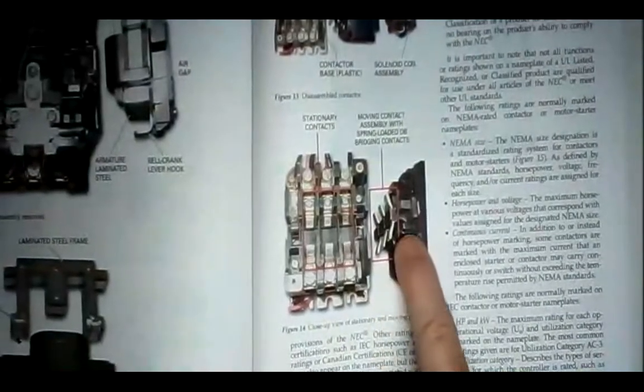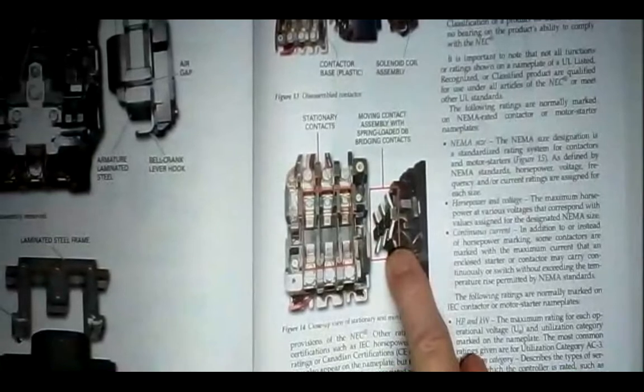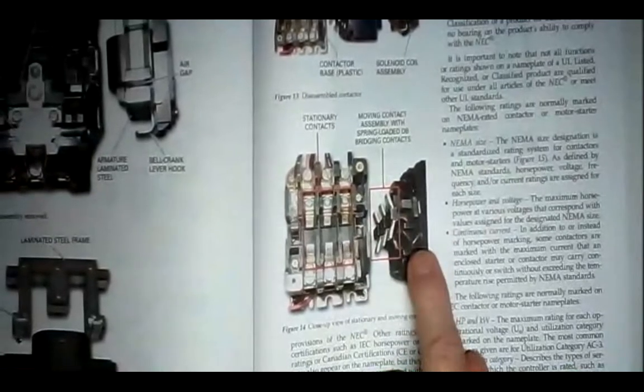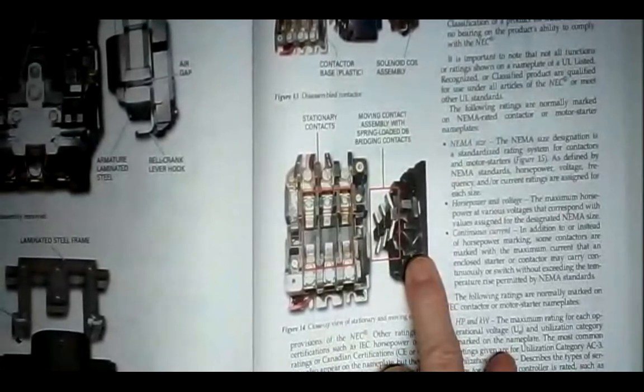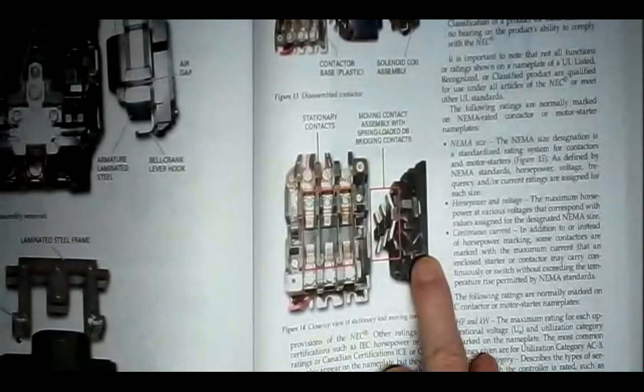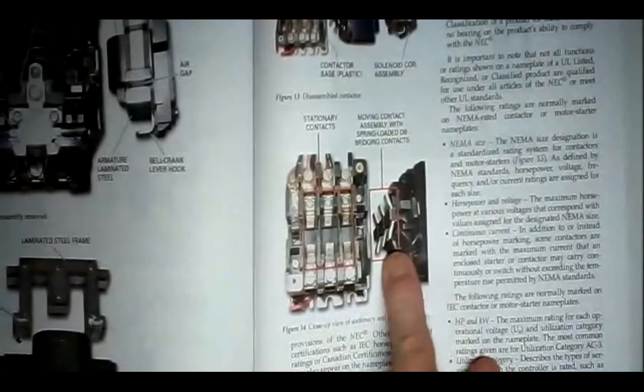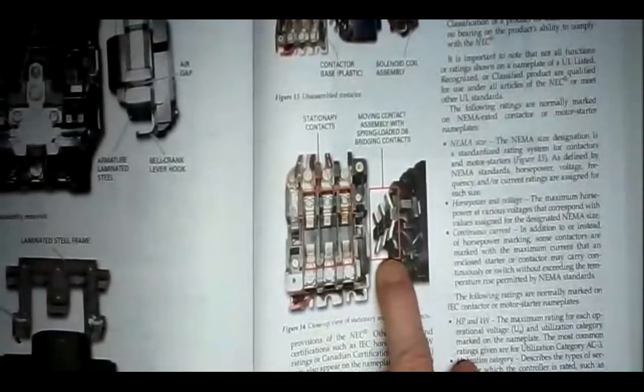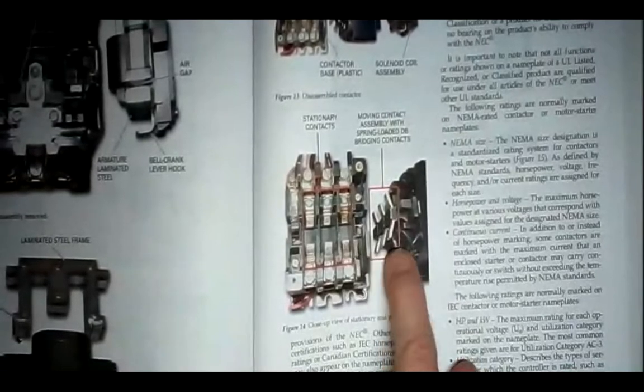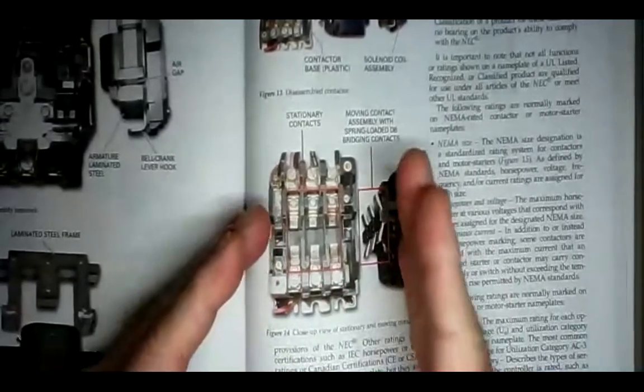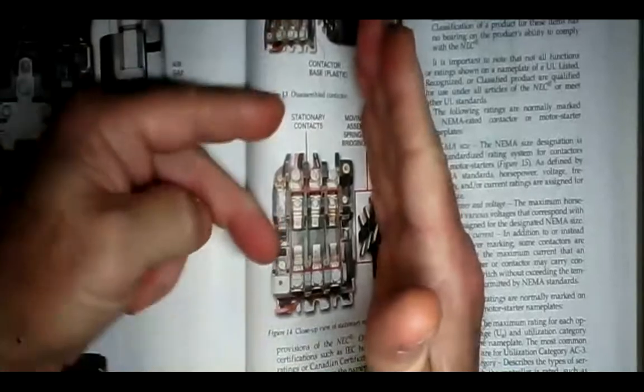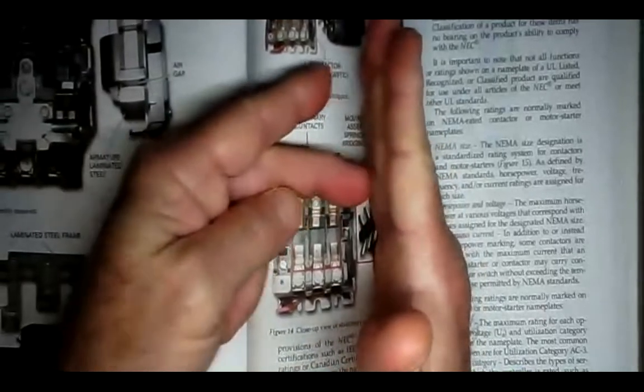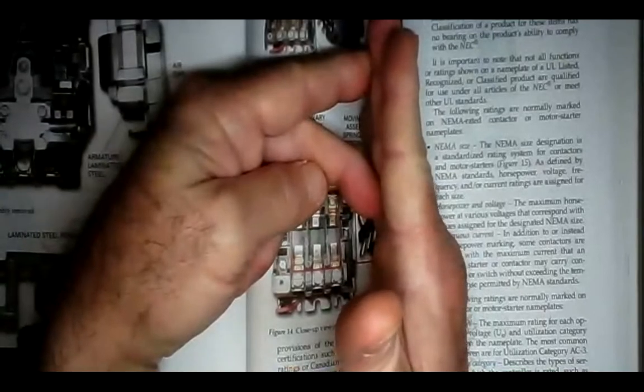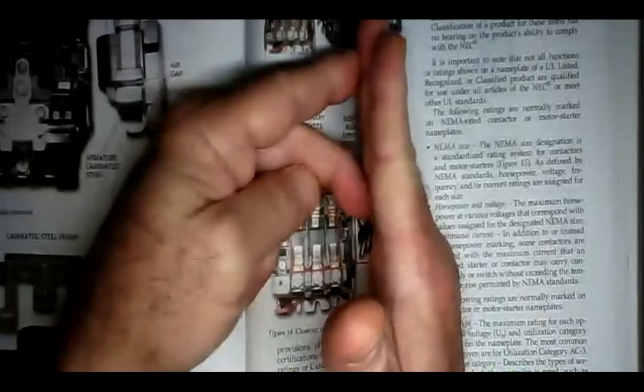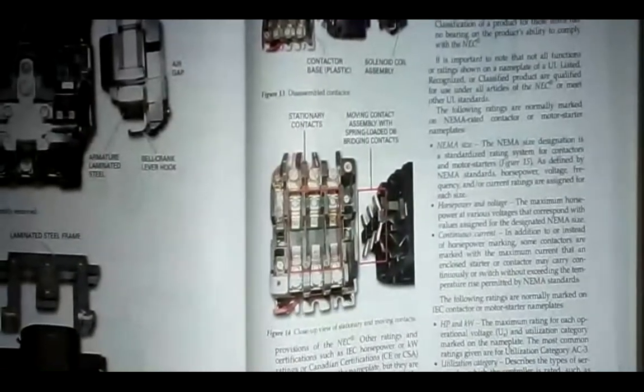Now, these are floating. They're on springs, and they float because it allows it to make a better connection. If they were rigidly connected to this contact bar, they may not line up exactly. You might have arcing and sparking. There may be a problem with them lining up. So they put them on springs. They allow them to float so that they will self-seat. They'll find their equilibrium. If one side comes down and touches the first contact, this spring allows it to roll and touch the other side as well. So that's why they're on springs, so that they can float, they can move around, and they will find their seating. Okay.